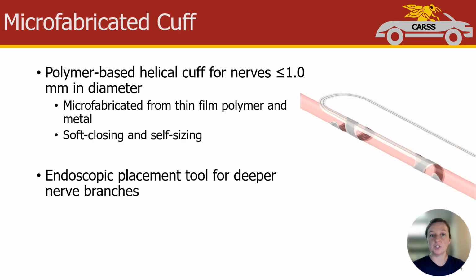To fill this technology void, we are developing a polymer-based helical cuff electrode for nerves less than or equal to 1 millimeter in diameter. A mock-up of the microfabricated cuff is shown in the image on the right, with the polymer backbone in white and metal electrodes and traces in gray, wrapped around a pink nerve. The device will be microfabricated from thin film polymer and thin film metal, and will be both soft closing and self-sizing. We will also build a surgical tool to allow for endoscopic placement of the cuff on deeper nerve branches.